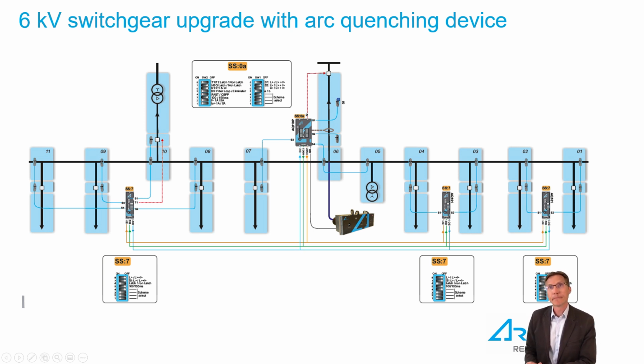Here, let's look at the implementation, how the actual quenching device implementation was done. Here in this same simplified principle picture, you will see all the components needed in putting the arc quenching device in use. That's all you need. So we do have point sensors installed for the arc detection. So arc light detection is achieved by the point sensors included in each compartment to be protected. Here, quite open spaced metal enclosed type of switchgear. So practically 2 sensors per bay is enough.